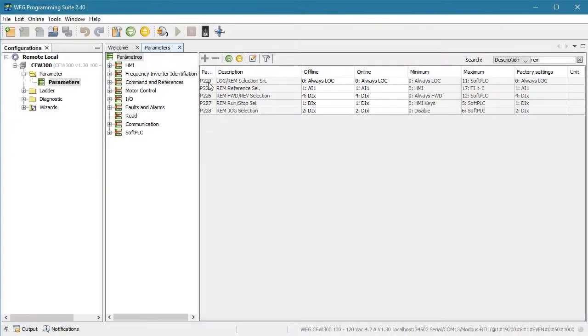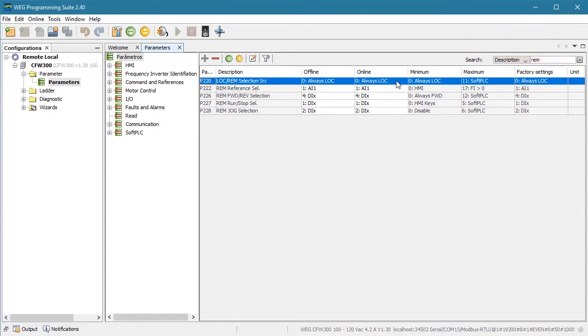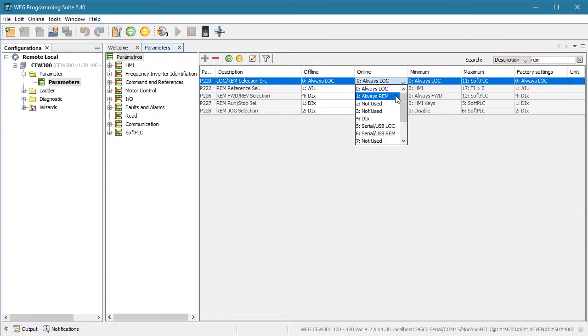If we look at parameter 220, which is the parameter that selects how local and remote modes are selected, we see it defaults to always local. To force it into remote mode, you simply set it to a 1.